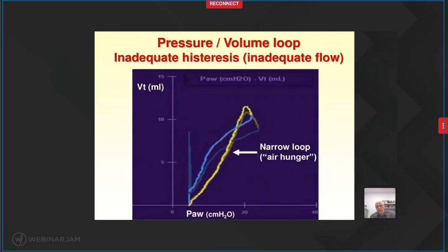Okay, this is another example of an abnormal pressure volume loop. As you can see here, not only is the hysteresis, which is the difference between the inspiratory and expiratory limb, too narrow, but you have an inverted loop here, meaning that the baby is really struggling to get an extra breath here. So the top part of this curve is done by the baby. That's why the inspiratory is more negative than expiratory. And this is usually due to air hunger. So you don't have enough flow here, and you need to increase your flow to be able to fix this.